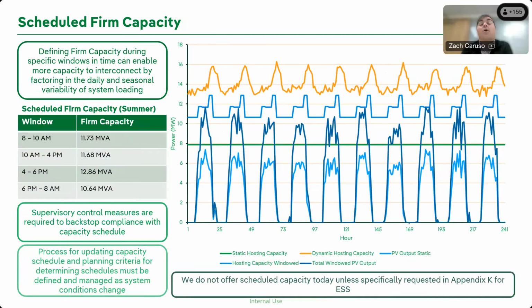So there are ways to do this via studies, by studying the sites in a way that gives you a profile that tells you, all right, between these hours my worst case scenario is this minimum load, so you can have X amount of capacity. And at these hours, in this bucket, I have this minimum load, and so you can have this capacity. You can see how one might break that out on the left here.